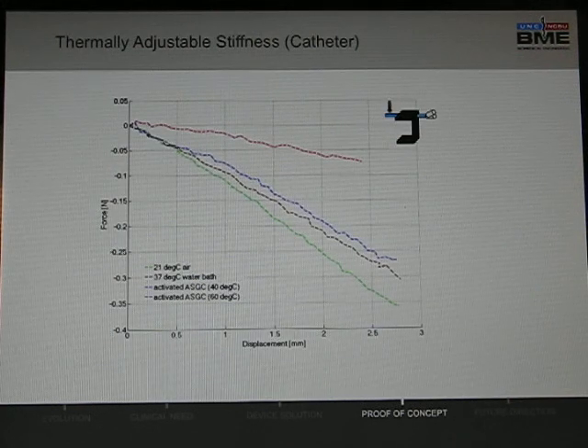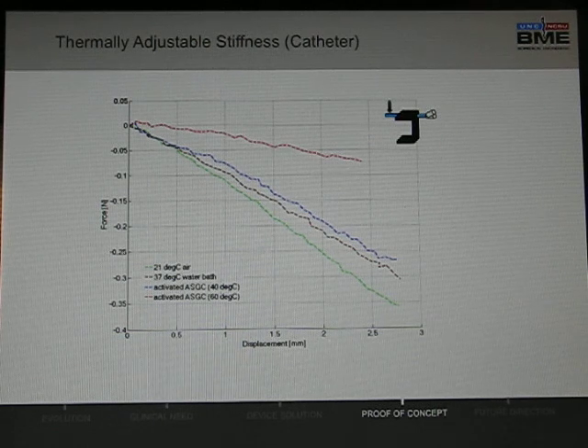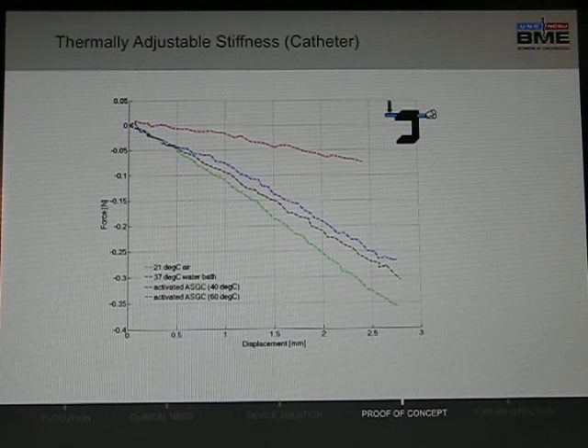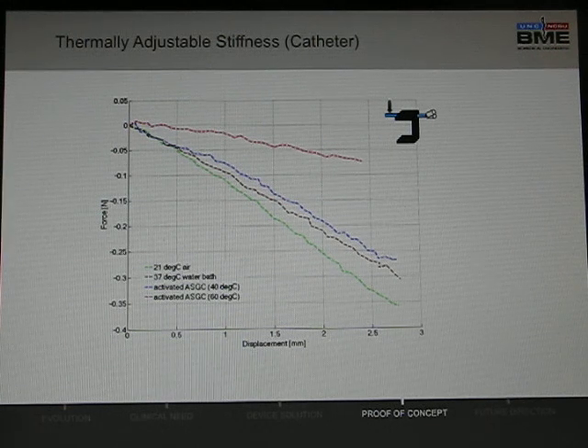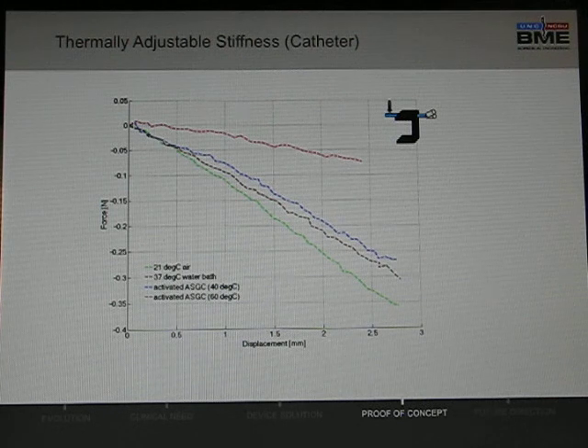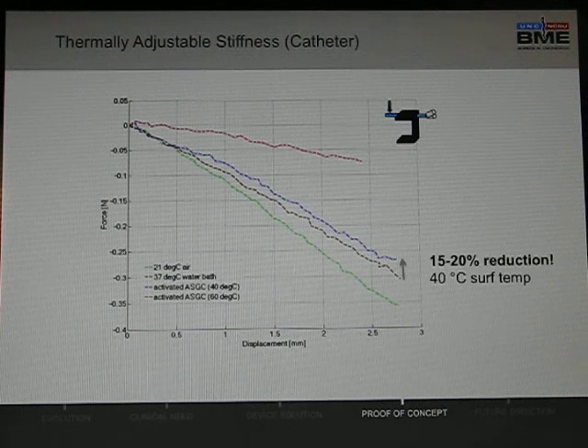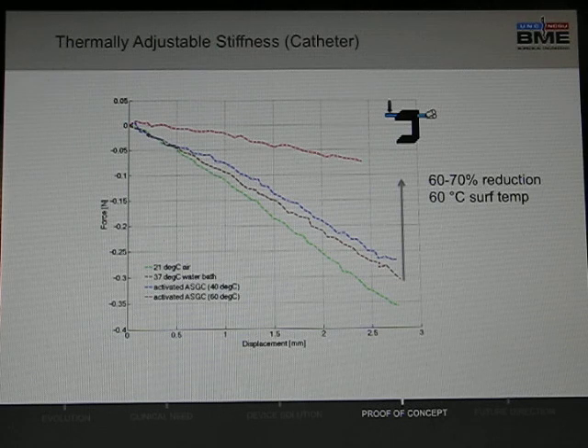Here we plotted force over displacement. The green trace represents the catheter in air at room temperature. The brown trace represents the catheter in physiological temperatures of 37 degrees C in a water bath. When the catheter is activated to get to a catheter surface temperature of approximately 40 degrees Celsius, we get approximately 15 to 20% reduction in force. If you remember, this spans the market catheter stiffness range. If we really juice up the catheter, get a surface temperature of 60 degrees C, you get approximately 60 to 70% reduction in force.